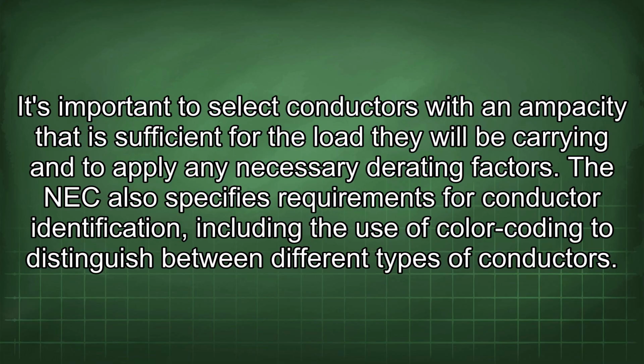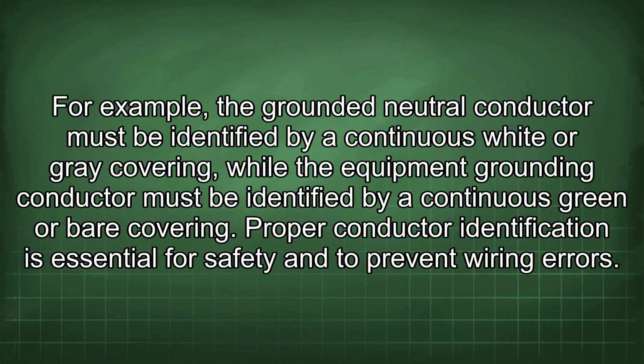The NEC also specifies requirements for conductor identification, including the use of color coding to distinguish between different types of conductors. For example, the grounded neutral conductor must be identified by a continuous white or gray covering, while the equipment grounding conductor must be identified by a continuous green or bare covering. Proper conductor identification is essential for safety and to prevent wiring errors.